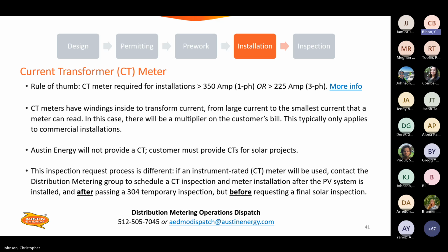We're here to talk about current transformer CT meters. Rule of thumb, CT meters are required for installations of 350 amps or over, single phase, or 225 amps or over, three phase. CT meters have windings inside them to transform current from large current to small current that a meter can read. In this case, there will be a multiplier on the customer's bill. This typically only applies to commercial installations.